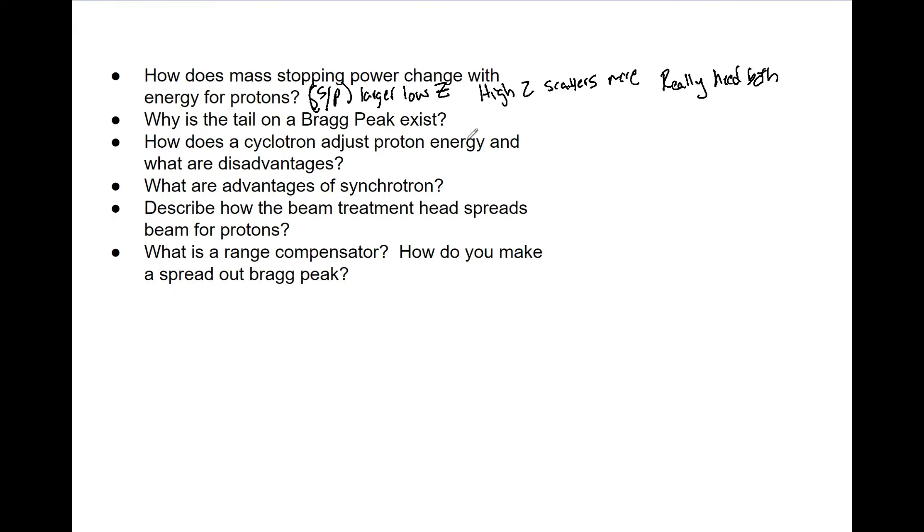So how does a cyclotron adjust proton energy and what are their disadvantages? It uses an energy degrader of plastic materials. Remember what we said: low Z materials slow protons down more than high Z. You're going to use a plastic material of various thickness in a wheel that alters the proton energy and range. The degraders cause neutrons, require more shielding, and have post-treatment radioactivity. Although they may be necessary to give you a range of energies, there are those three big disadvantages.